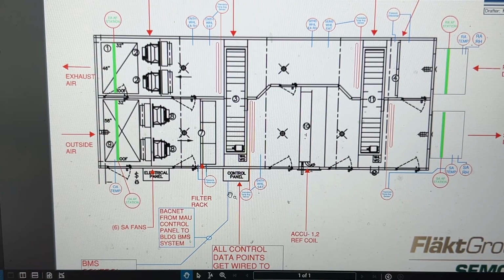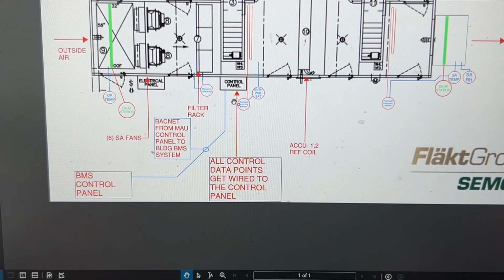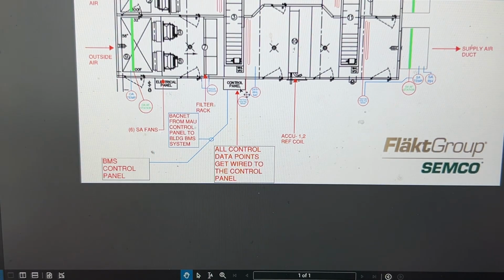So from that control panel, as far as the BMS goes, we've got a BACnet from that unit control panel to the building's BMS system. So that's an Ethernet connection that pulls all these data points from it and takes it over to the house control panel so that it can be added to the building graphics. So this unit is self-sustaining. So based on your airflows and the temperatures, it regulates itself 100%. The graphics are just showing that to the BMS system. So the BMS system doesn't have control of this unit.